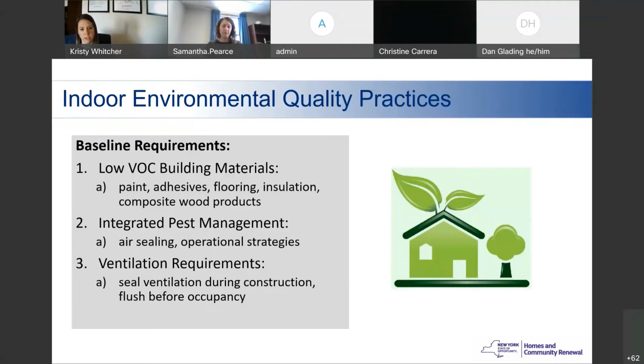One of the new additions addresses protecting ventilation equipment and ductwork during construction, including measures to seal all ventilation during construction and flush the system prior to occupancy. This requirement also aligns with some of the green building standards many projects have already been pursuing.